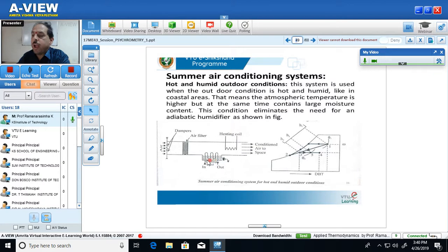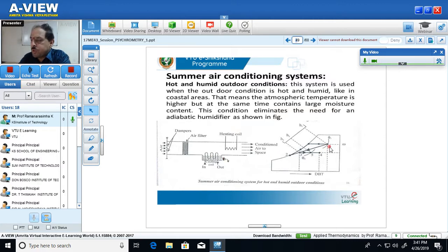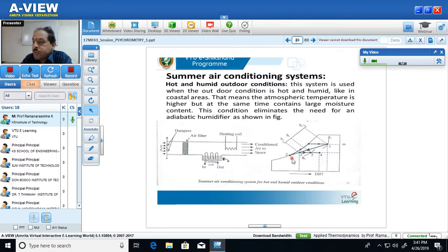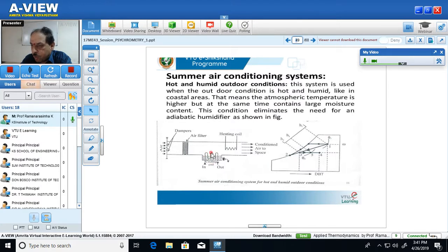Two things are happening: temperature of air is decreasing, and specific humidity is also decreasing. On the psychrometric chart, if you move from point 1 horizontally to the saturation curve, that is the cooling process. From that point on the saturation curve, moving to point 2 is the dehumidification process. So two things occur in this section: cooling and removal of excess water from the air, which we call the dehumidification process.